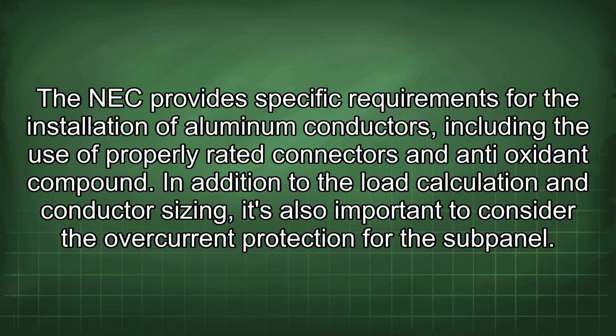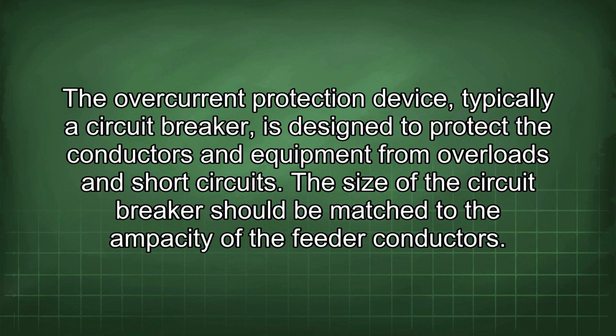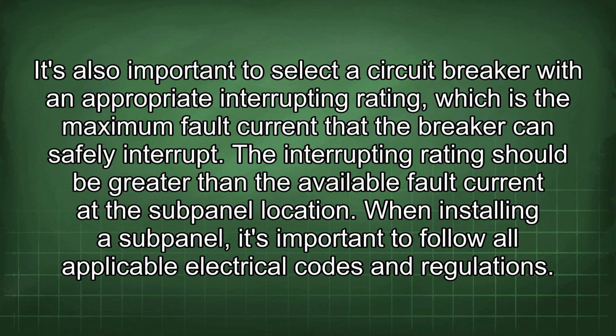protection for the subpanel. The overcurrent protection device, typically a circuit breaker, is designed to protect the conductors and equipment from overloads and short circuits. The size of the circuit breaker should be matched to the ampacity of the feeder conductors. It's also important to select a circuit breaker with an appropriate interrupting rating, which is the maximum fault current that the breaker can safely interrupt. The interrupting rating should be greater than the available fault current at the subpanel location.